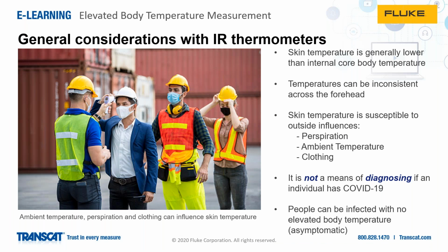So, general considerations for IR thermometers: your skin temperature is going to be lower than your internal body temperature, and that's the reason for having the offset that exists both in the IR thermometer and most of the TI camera systems, and in general temperatures can be inconsistent across the forehead.